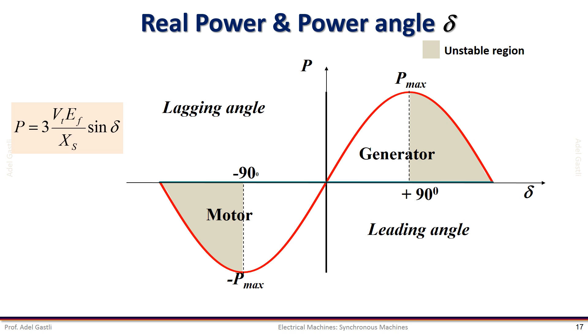This figure displays graphically the variation of active power P versus the power angle for both motor and generator operating modes. The positive angle refers to generator action and negative angles refer to motor action. The regions shaded in gray are unstable regions. If a synchronous motor tends to pull out of synchronism because of excessive load, the field current can be increased to develop higher torque to prevent loss of synchronism. Similarly, in a synchronous generator, if the prime mover tends to drive the machine to super-synchronous speed by excessive driving torque, the field current can be increased to produce more counter-torque to oppose such a tendency.